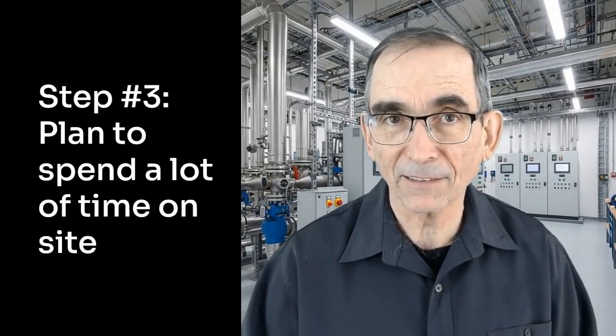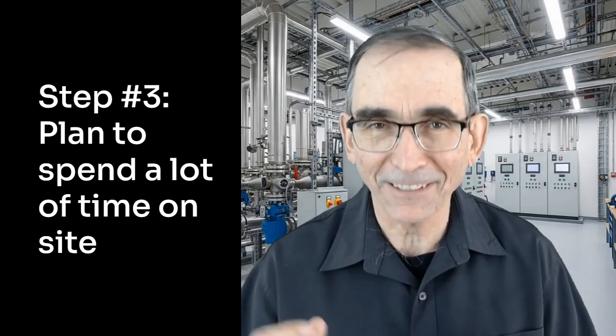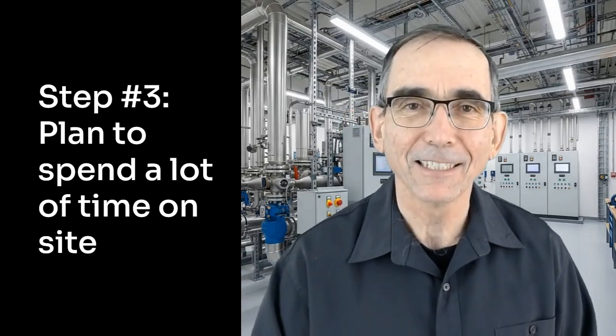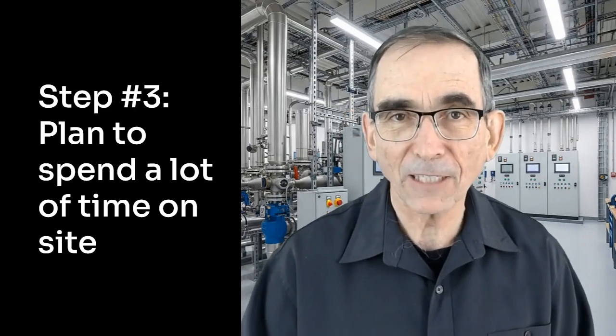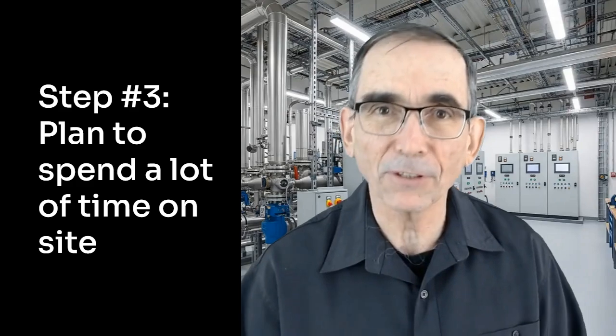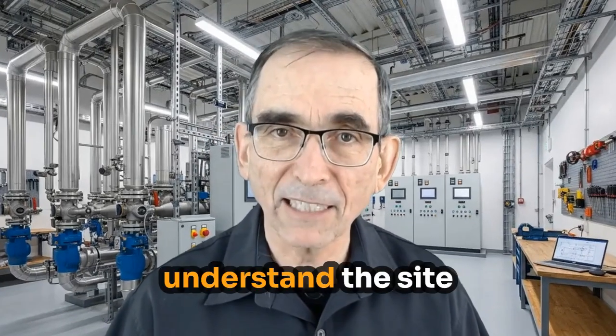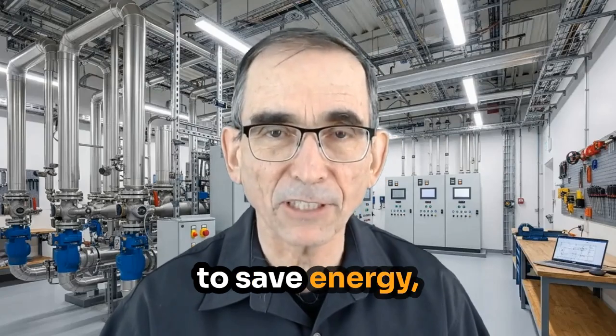Step three is to plan to spend a lot of time on site. Now, whilst many auditors favour a half-day or a one-day walkthrough, in my experience, many sites require more time than that on site to be able to really understand the site and the opportunities to save energy. You need to bring the right tools: light meter, infrared camera, data loggers, computer, phone for taking photos, and ask for a desk where you can do preliminary analysis. Don't just show up with just a tablet or clipboard.